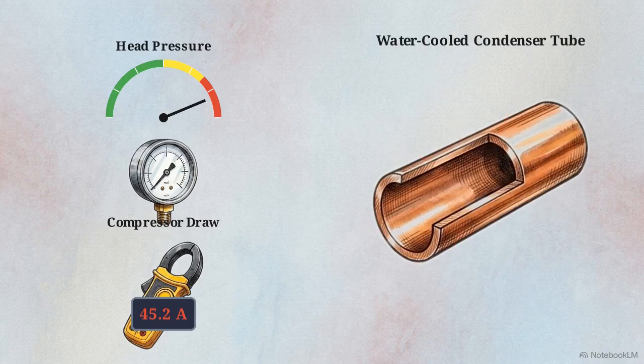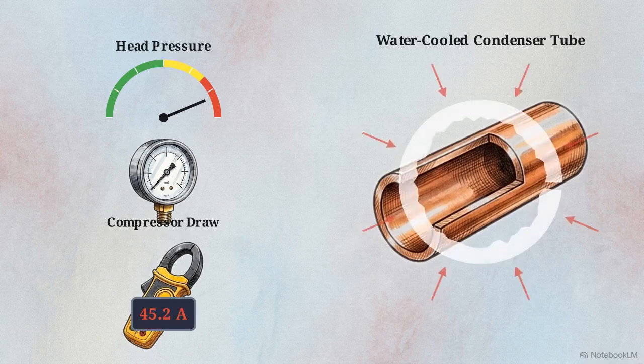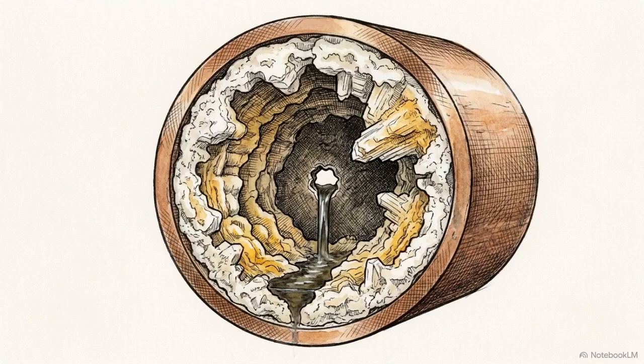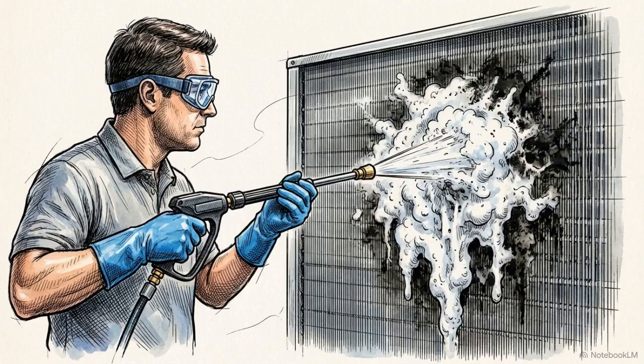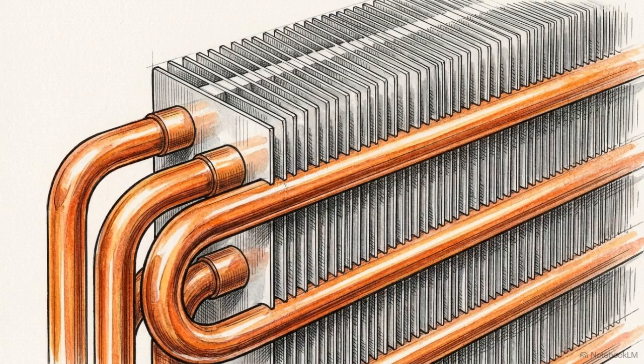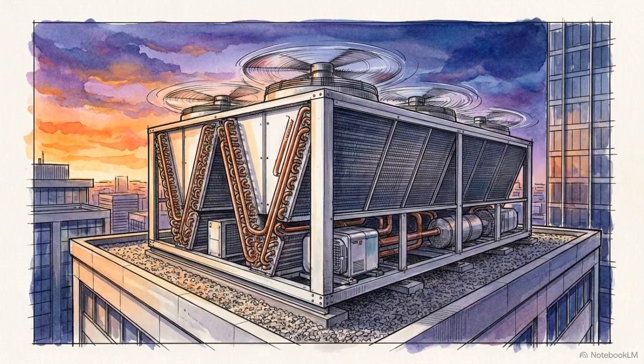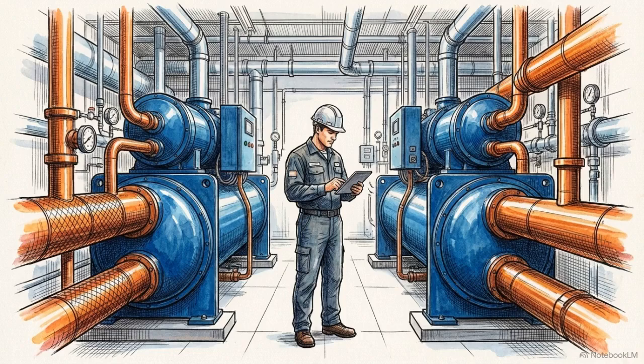The equivalent failure in water-cooled systems is scaling. Over time, heavy mineral deposits build up inside the water tubes. This mineral scale acts as a hard insulator. It destroys the condenser's approach temperature, blocking thermal transfer and causing high-pressure systemic failure, just like dirty fins. Preventive maintenance, cleaning air coils, verifying fan motor speeds, and treating cooling water is rarely about fixing broken parts. It is the active preservation of the system's precise thermal geometry. The condenser is the absolute arbiter of system capacity. By mastering its thermodynamic limits, material constraints, and physical architectures, a technician ensures the entire refrigeration cycle continues to breathe.